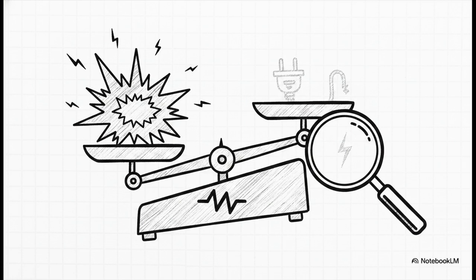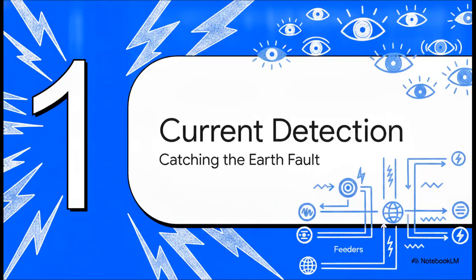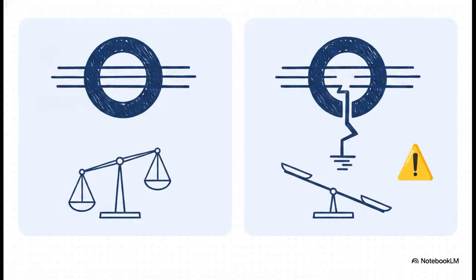Here's the catch, though. Because that current is limited and stable, it is inherently way harder to detect. So how does the protection system actually spot a fault happening somewhere deep in the plant? Well, let's start with catching the earth fault through current detection. These are the primary sensors deployed on every feeder and generator. Now, what's really interesting about this is how brilliantly simple the physics actually are.